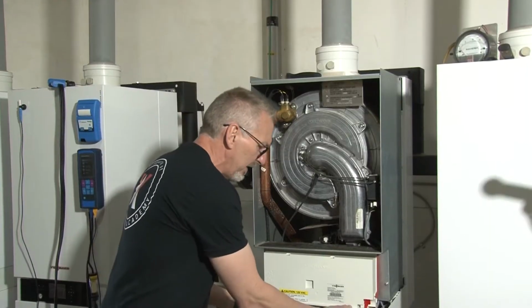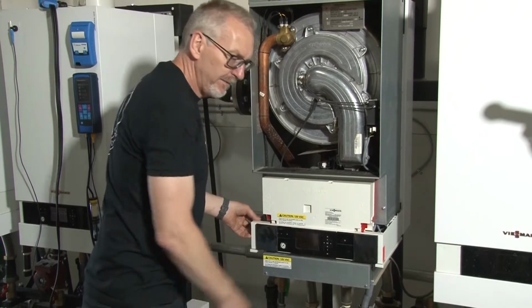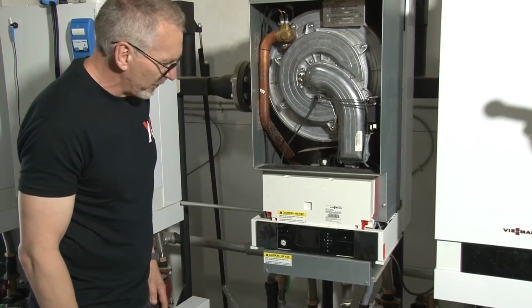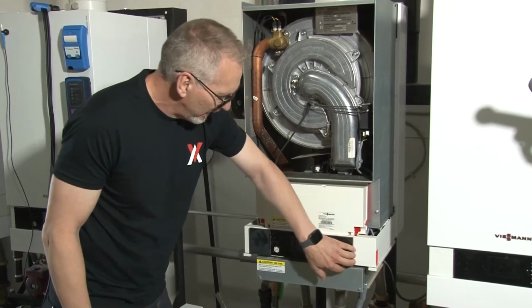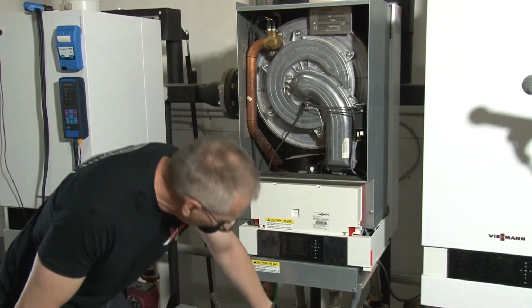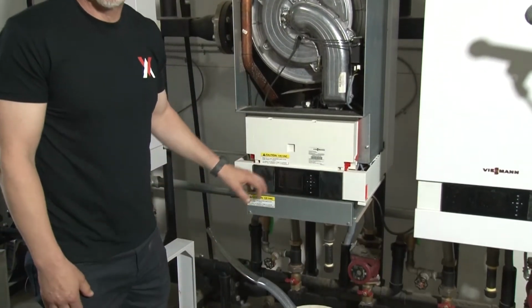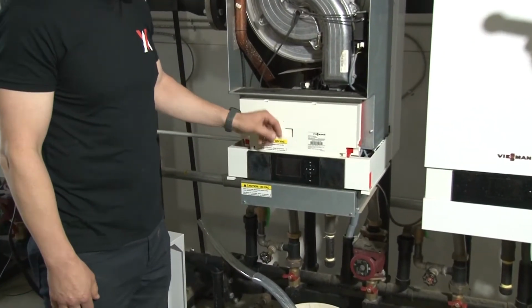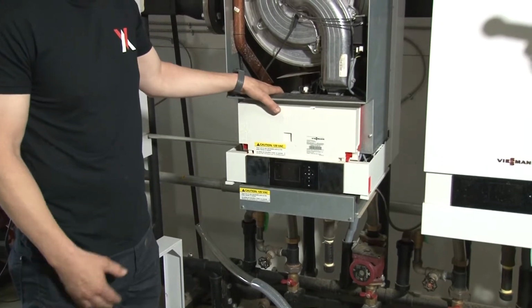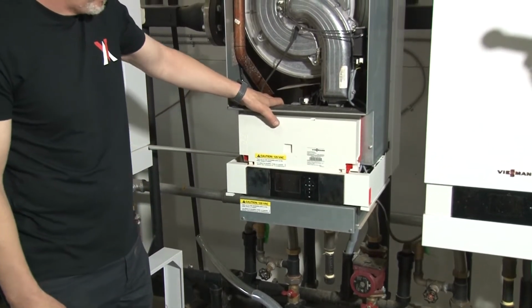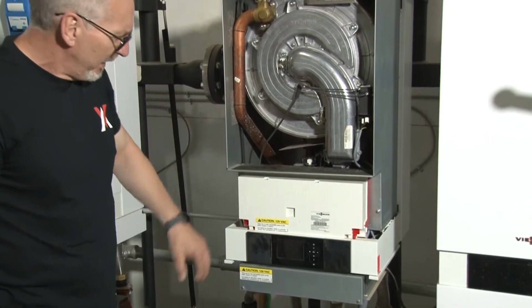So the first thing is power off. Right, make sure the screen is off here. There's no power to the burner, that's important. And your gas connection on the bottom here, we have to make sure that's isolated, it's off, right? So we're going to be pulling the gas line off of this. We don't want that gas puking into the boiler room, not a good thing if we're doing that.